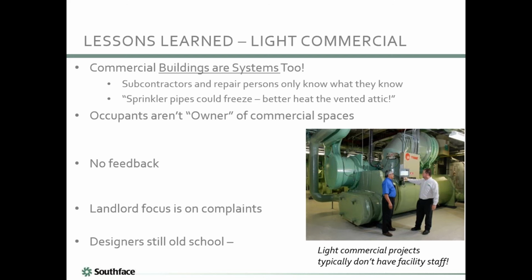It underscores the issue that we often see, which is you've got buildings that have been around for many years. They may have changed in use and in occupancy over time. So you've had one approach to solve a problem or make the building perform better for one purpose, and then a few years down the line, you see another one. You end up 20, 30 years into the existence of the building, and you've got some strange decisions that may have been made, such as heating a vented attic. Because if we added sprinklers at some point, we certainly wouldn't want those to freeze, so let's just heat the attic.